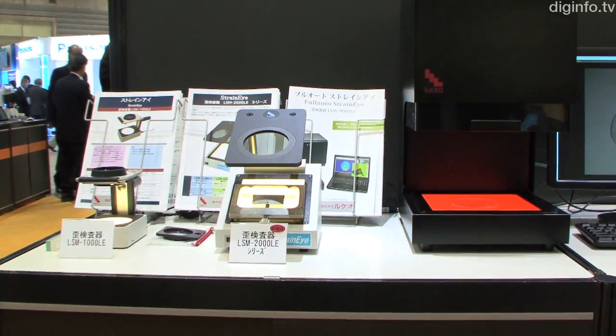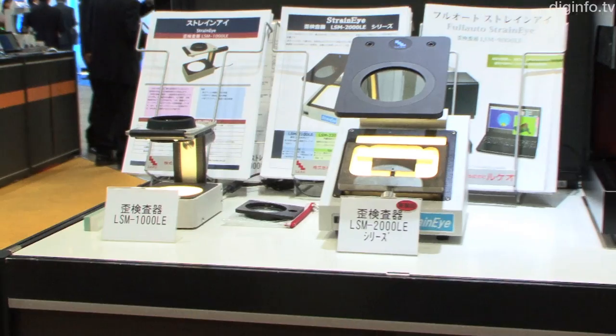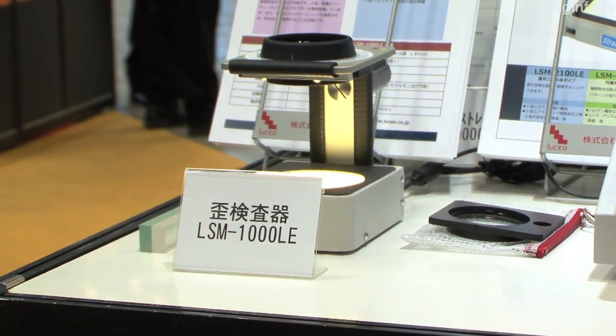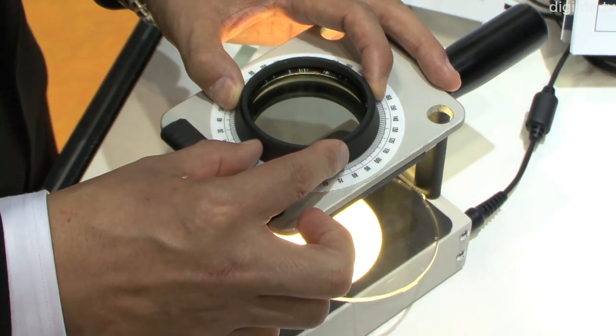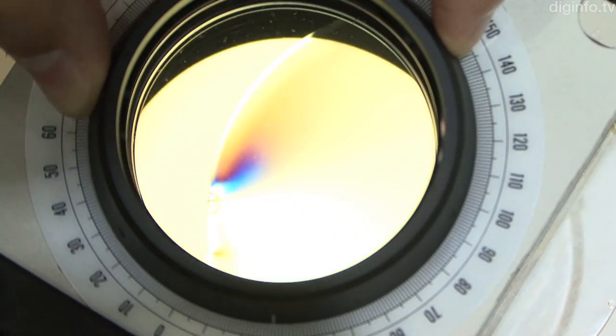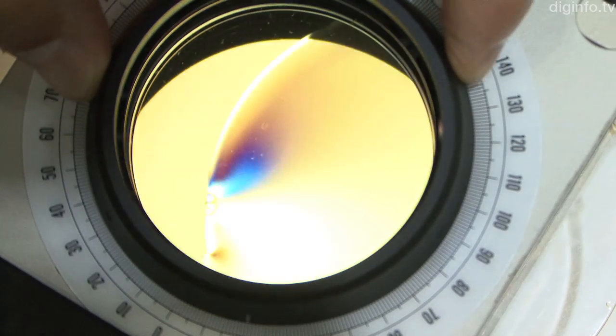Until now, the mainstream devices for measuring strain have been visual observation type strain testers that use the Senarmont method. With the Senarmont method, an operator rotates the analyzer to change the brightness of the measurement location, and the degree of strain is then measured by the rotated angle.